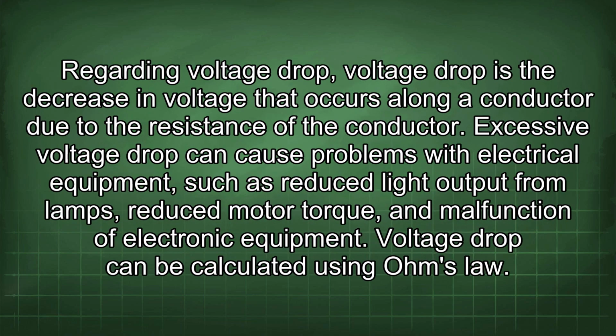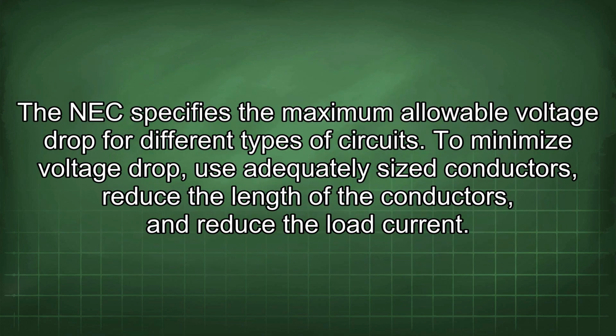Regarding voltage drop, it is the decrease in voltage that occurs along a conductor due to the resistance of the conductor. Excessive voltage drop can cause problems with electrical equipment, such as reduced light output from lamps, reduced motor torque, and malfunction of electronic equipment. Voltage drop can be calculated using Ohm's law. The NEC specifies the maximum allowable voltage drop for different types of circuits. To minimize voltage drop, use adequately sized conductors, reduce the length of the conductors, and reduce the load current.